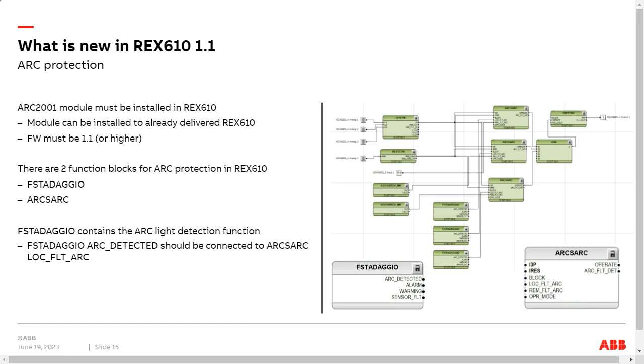And then we have the alarm signal. Basically there is a parameter, so if this arc detected has lasted beyond a certain interval, I think from 1 second to 60 seconds, this alarm signal will be triggered. For example, if there is a continuous arc and it hasn't gone back to normal after this set time, I think the default is 10 seconds, the alarm signal will activate. Typically that would mean you have some issue of some kind. I don't want to go into details on that because it can be many different things.